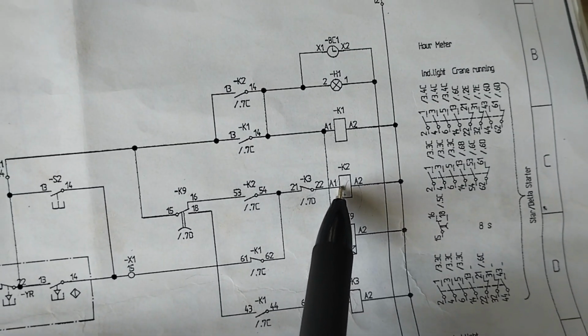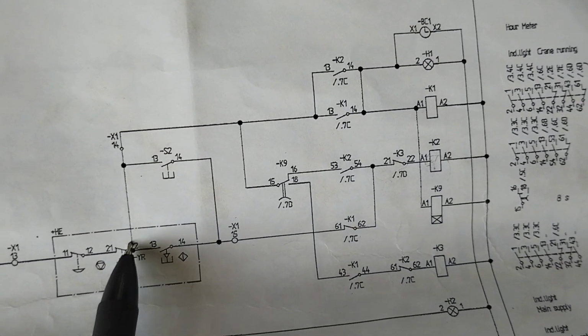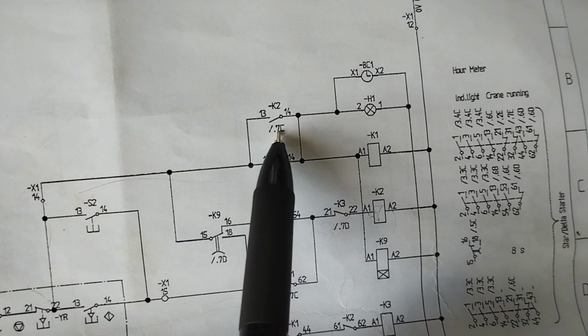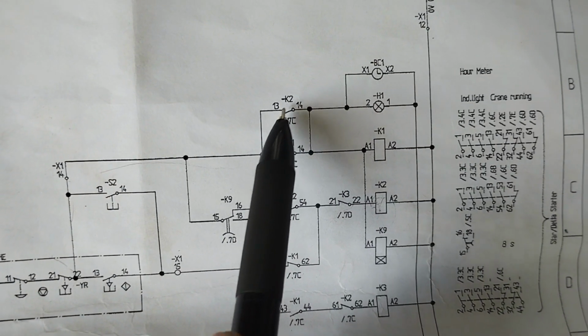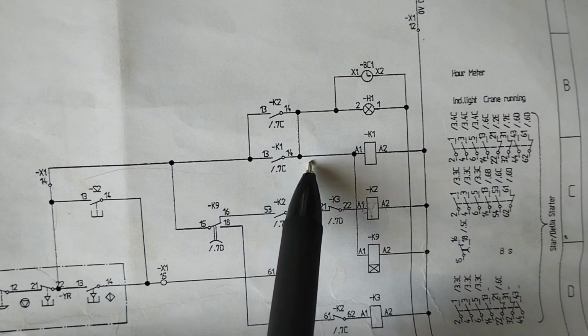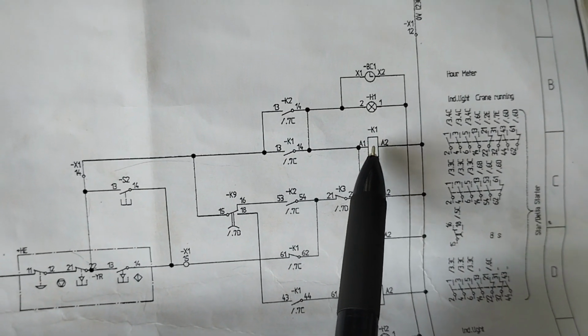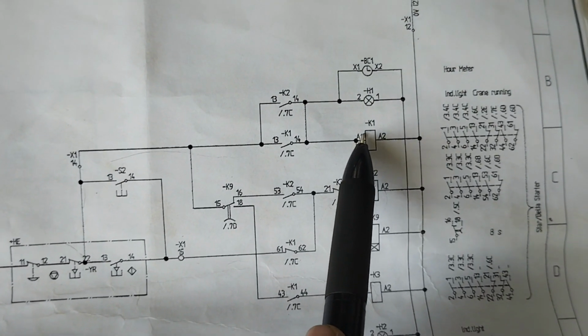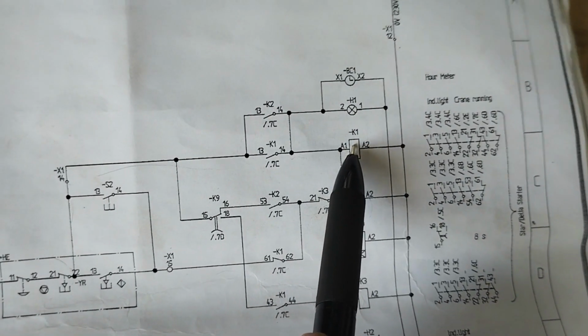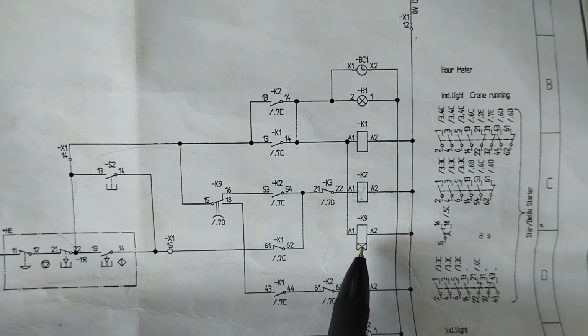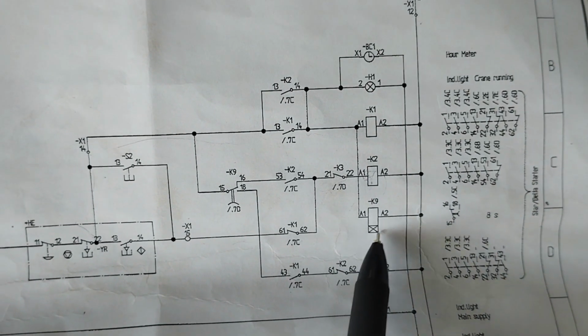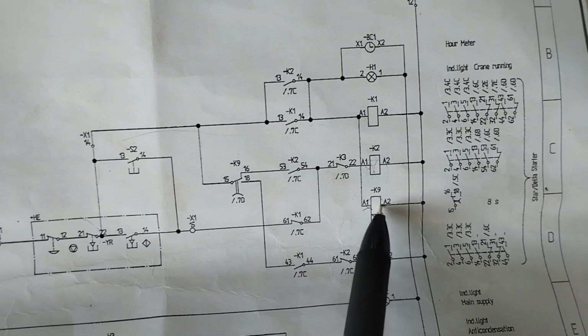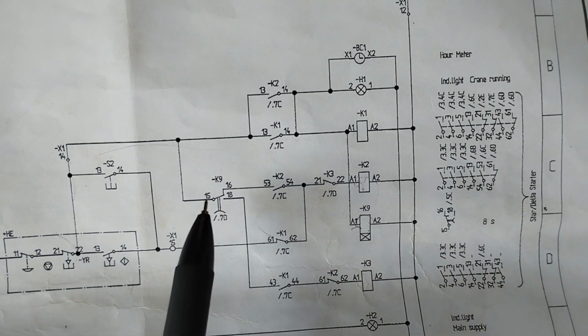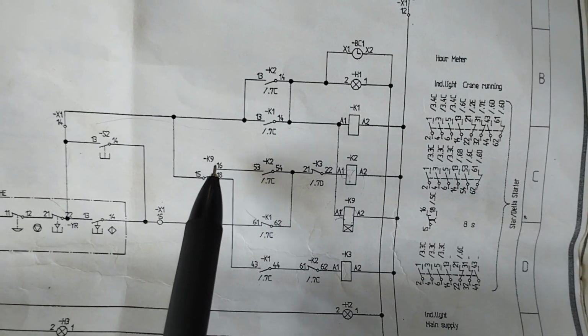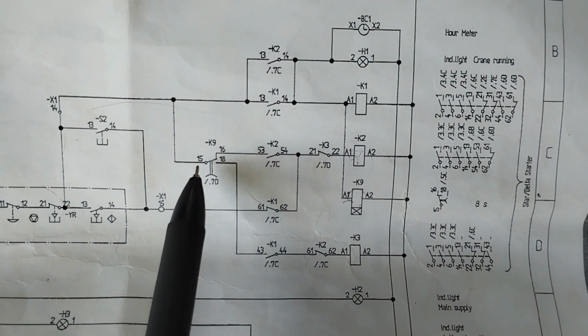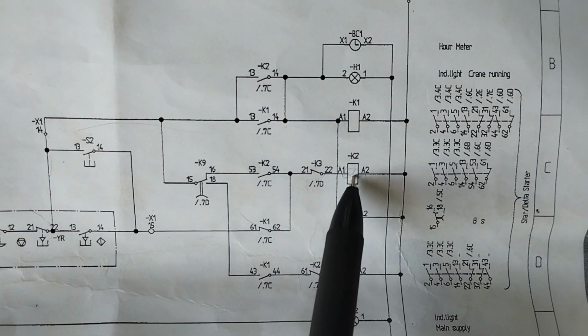K2 energizes, the star contactor energizes. After K2 energizes, you can see here power is already coming like this. K2 energized, so the normally open contact of K2 will get closed and power will transfer like this, and K1 will energize. K1 is the main contactor of the motor. Okay, so now K2 and K1 are energized, and the motor runs at reduced speed. At the same time K9, the timer, is also energized for 5 seconds. So after 5 seconds what will happen? After 5 seconds you can see this is the timer contact, 15, 16 normally closed and 15, 18 normally open. So after 5 seconds 15, 16 will open, and K2 will de-energize.